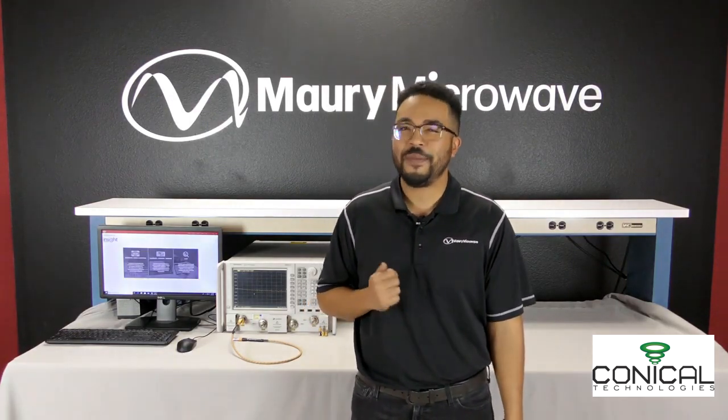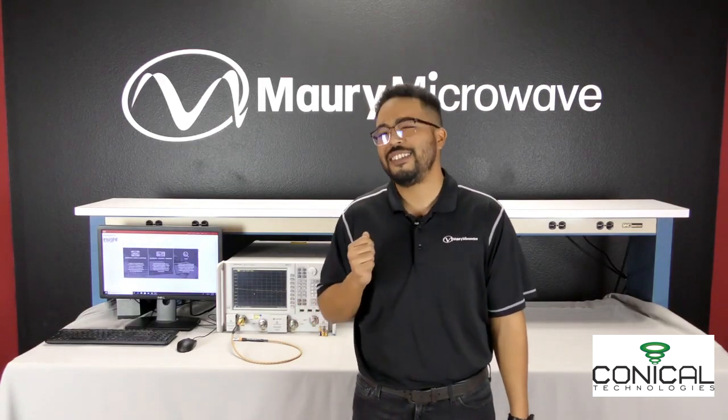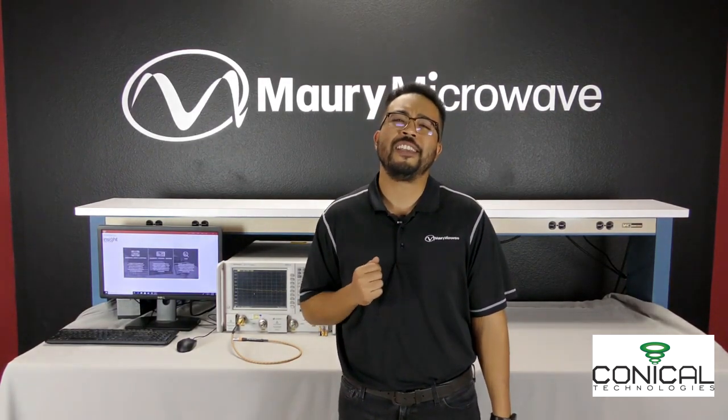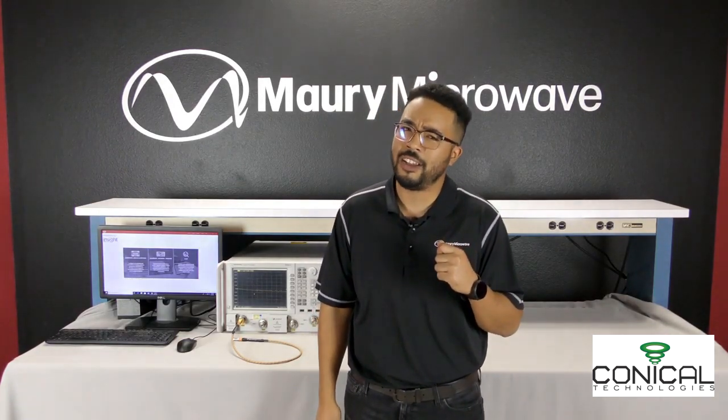Cable isn't binary. It doesn't work one day and then stops working the next day. Its degradation is slow. At some point, its performance changes ever so slightly and adds a little error to your measurements. It may be negligible at first, but as the cable continues to degrade, the errors get larger and larger until one day you realize that something doesn't look right.